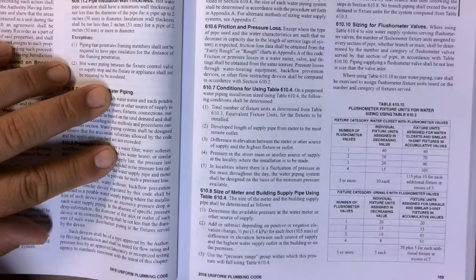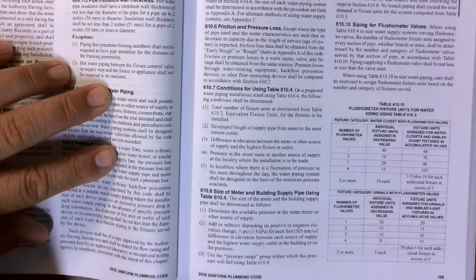The size of the meter and the building supply shall be determined as follows. Number 1, determine the available pressure at the water meter, right? So we figure out what our minimum pressure is. Add or subtract, depending on positive or negative elevation, a half a pound for each foot of difference in elevation between such source of supply and the highest water supply outlet in the building or on the premises. So let's say it's 10 feet high. We have the meter, and then the highest fixture is 10 feet above the meter. We are going to subtract from our minimum pressure. You have 5 PSI.